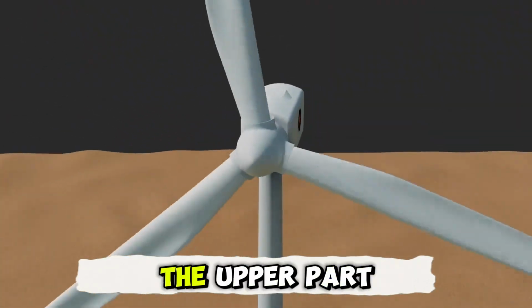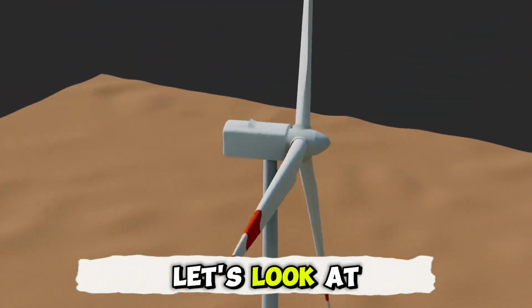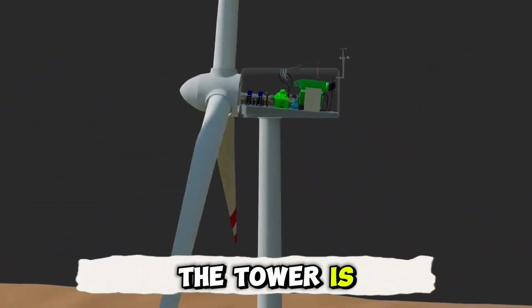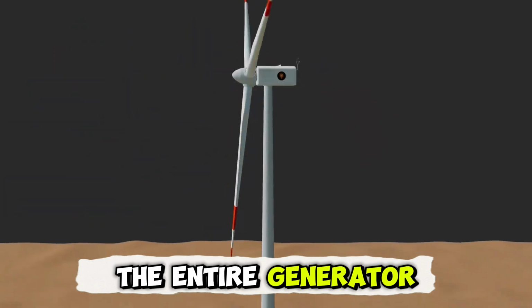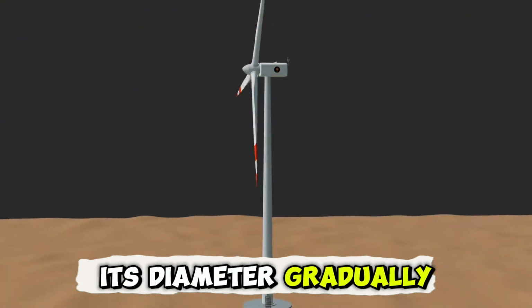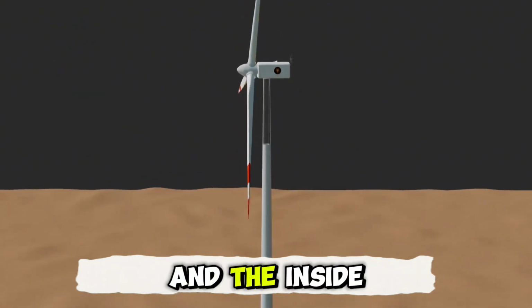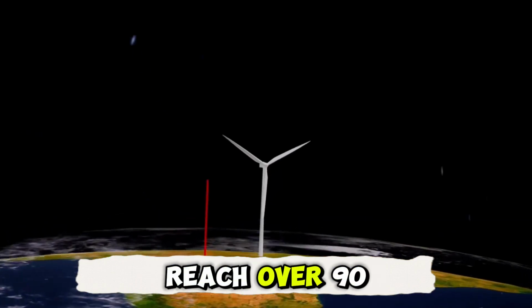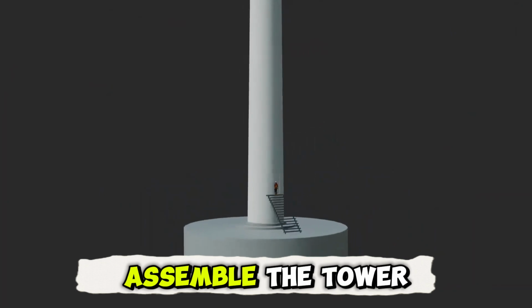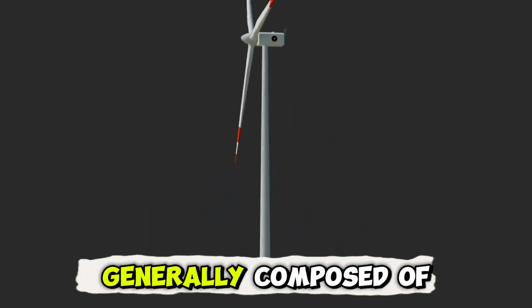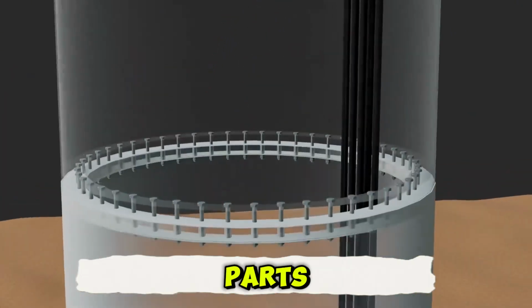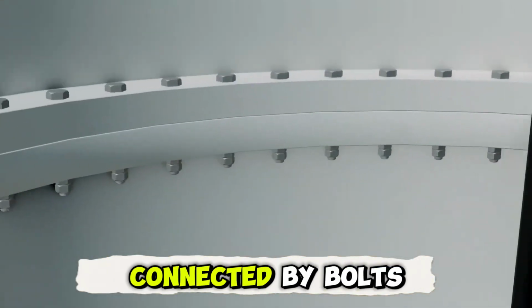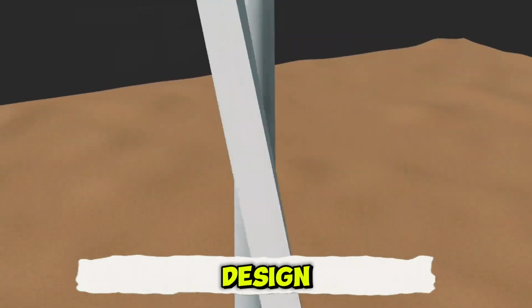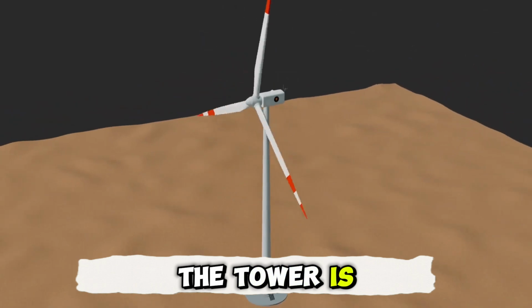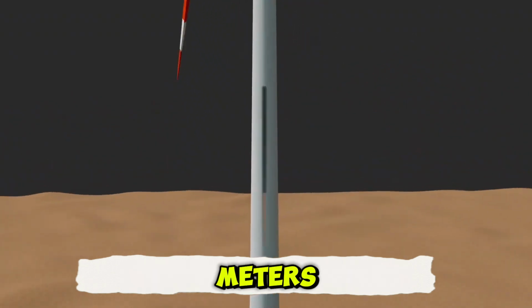After talking about the upper part of the wind turbine, let's look at its tower. The tower is the support for the entire generator set. Its diameter gradually shrinks from the bottom up, and the inside of the tower is hollow. The height of each tower can reach over 90 meters. In order to assemble it, the tower is generally composed of 3 to 4 parts. Each part of the tower is connected by bolts. Depending on the design, the diameter of the tower is usually around 4.8 meters.